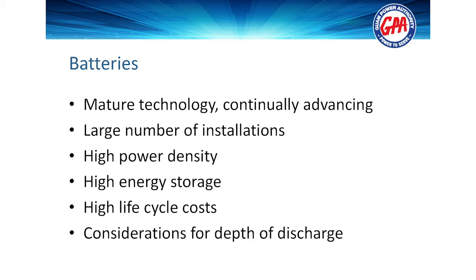Batteries. Batteries have been around for a long time. In Alaska, we've successfully used batteries on a number of installations. We used to have the largest battery installation in the world for many years. We have a 40 megawatt battery that's designed as a deep discharge battery. Its improvement to the Alaskan grid is just immeasurable. When that battery is out of service, everybody knows it. But they have a high life cycle cost. That battery system is about 10 years old now. They're starting to replace batteries, they're starting to replace strings. It is an expensive system to maintain, but its benefits are huge. Okay, next.